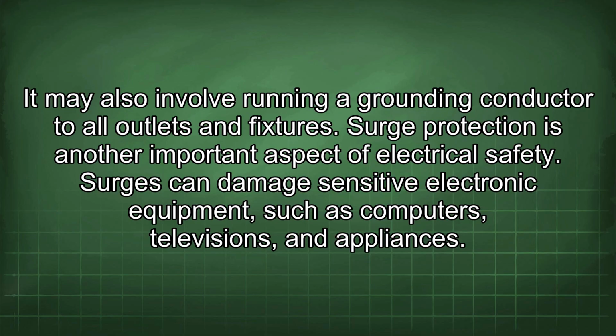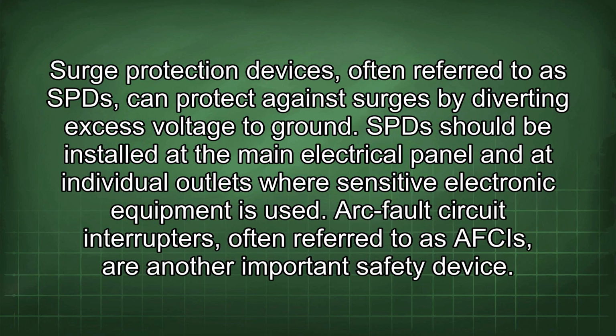Surge protection is another important aspect of electrical safety. Surges can damage sensitive electronic equipment such as computers, televisions, and appliances. Surge protection devices, often referred to as SPD, can protect against surges by diverting excess voltage to ground. SPD should be installed at the main electrical panel and at individual outlets where sensitive electronic equipment is used.